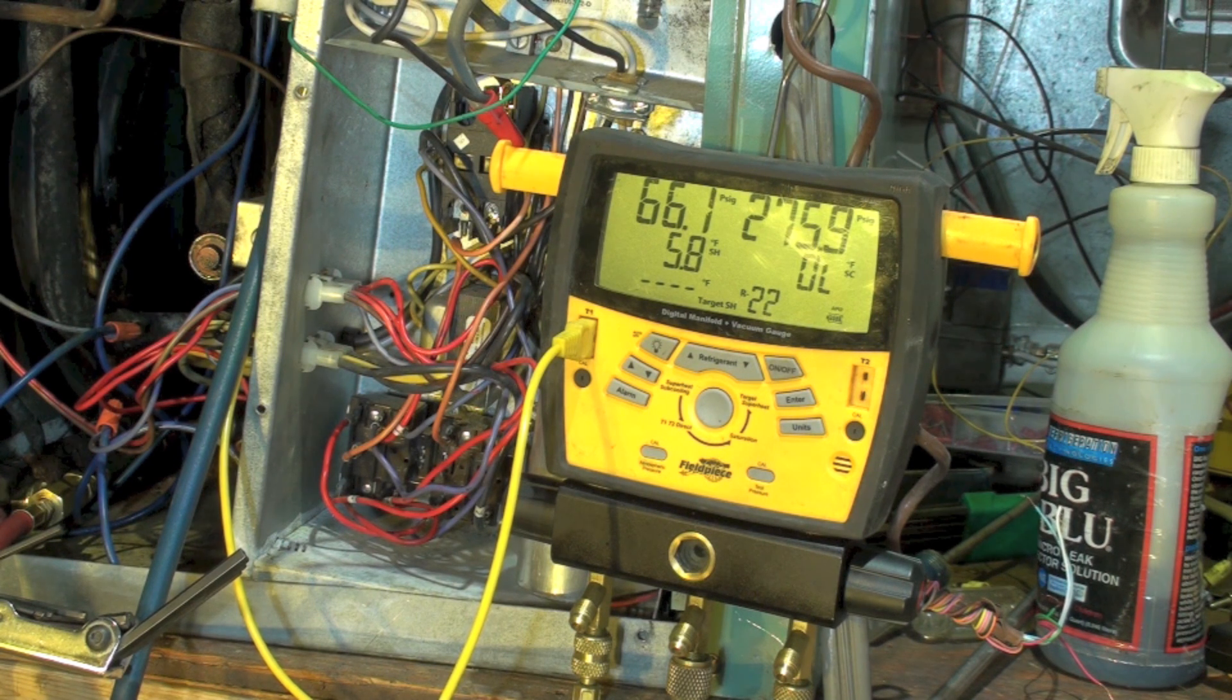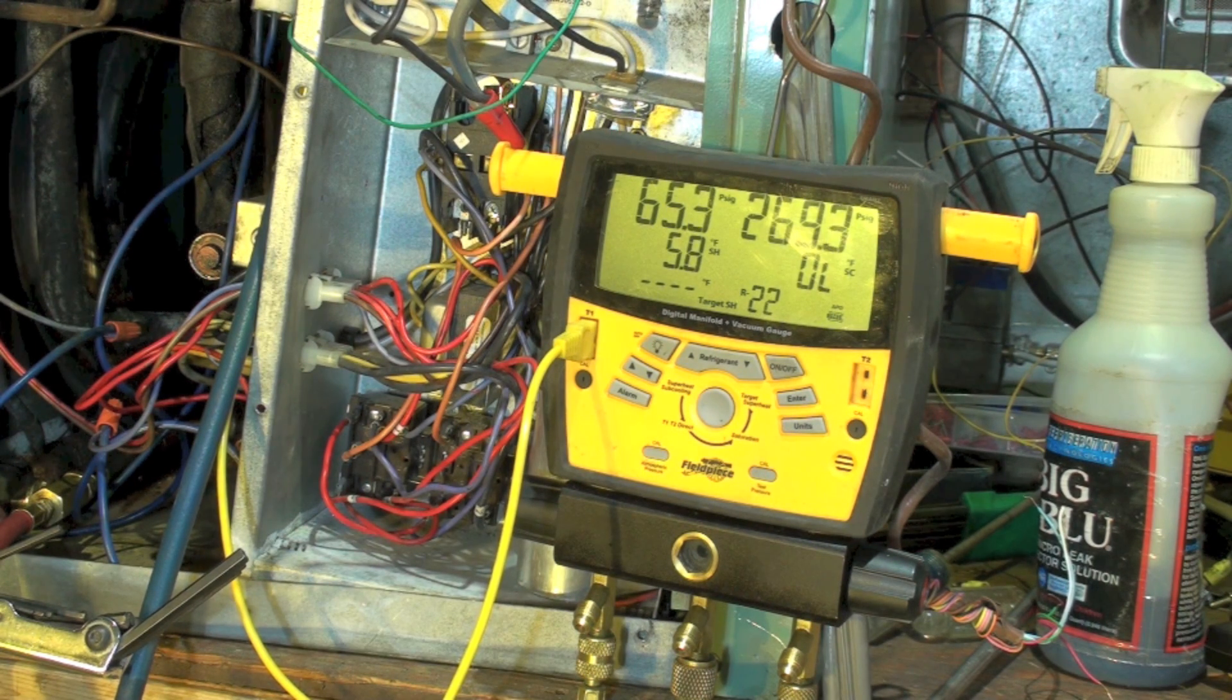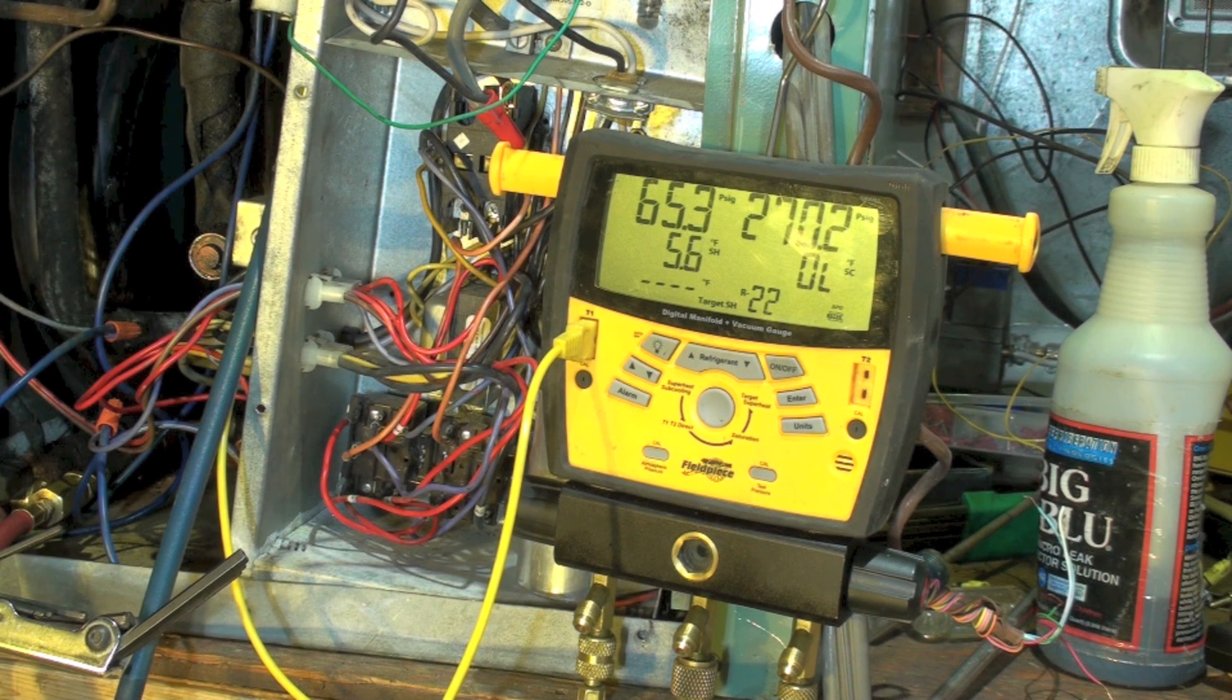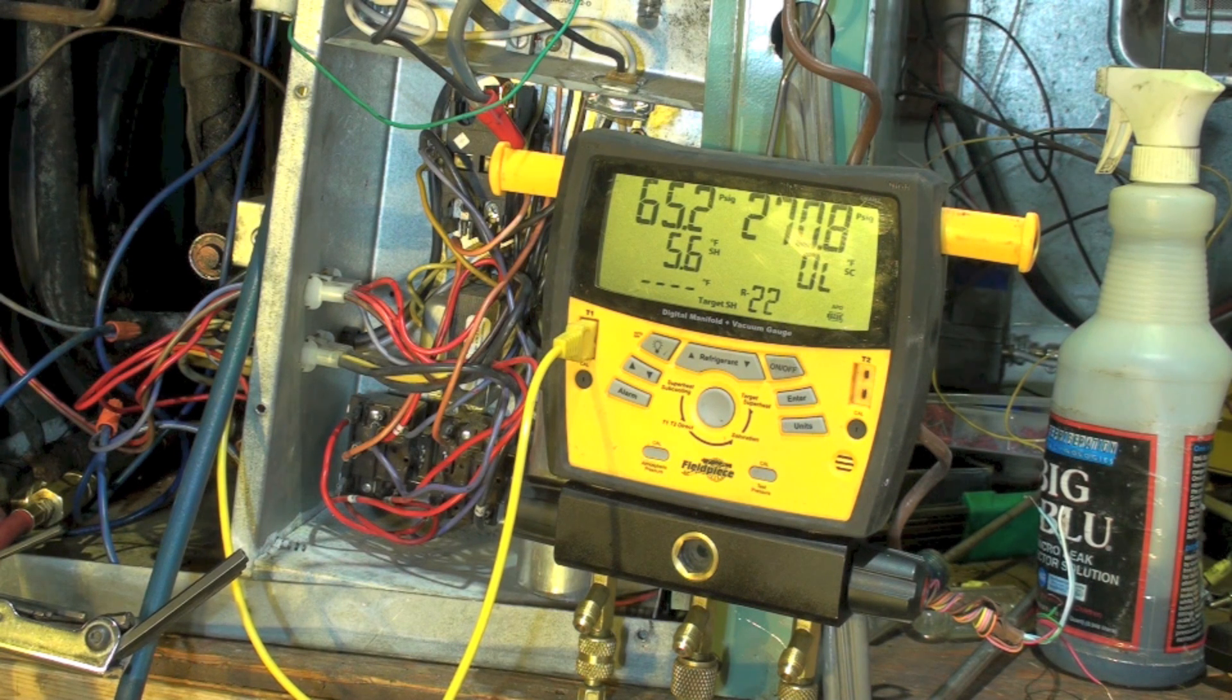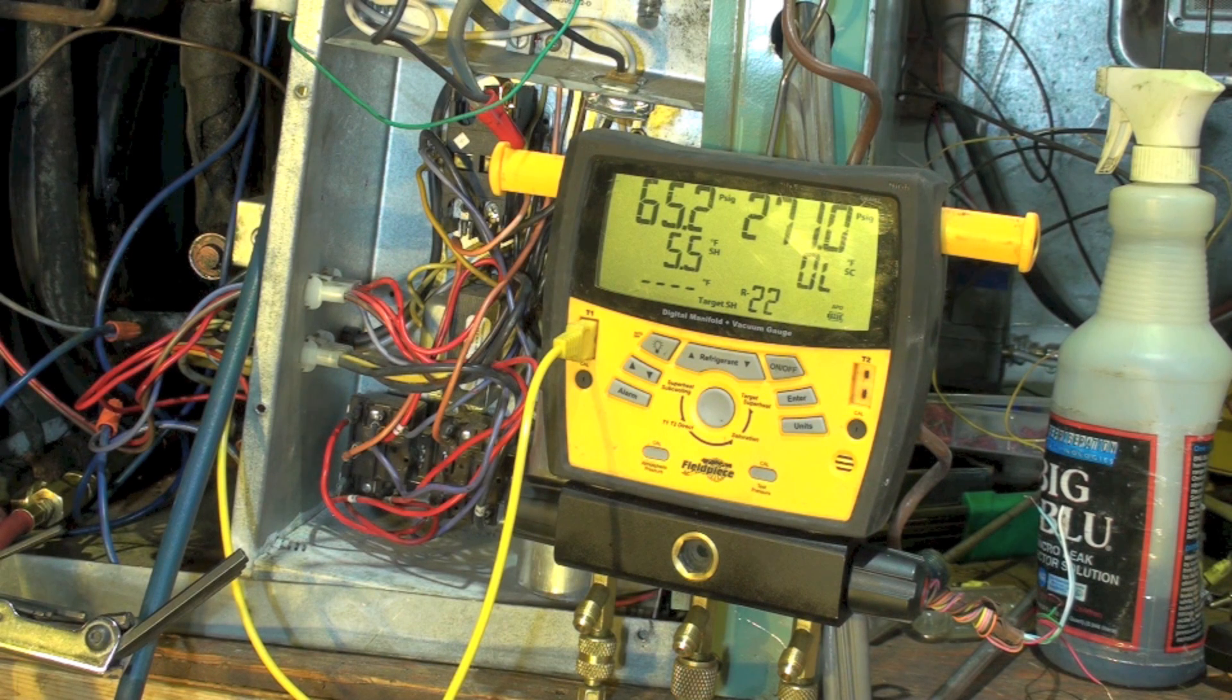Now the head pressure is pretty high here and our superheat is really low too. Now this is a cap tube feed, so the suction pressure is in direct relation to the head pressure - the higher the head pressure, the higher the suction pressure. That's a pretty high head pressure, and one of the interesting things about these things is I can pretty much dial whatever head pressure I want.